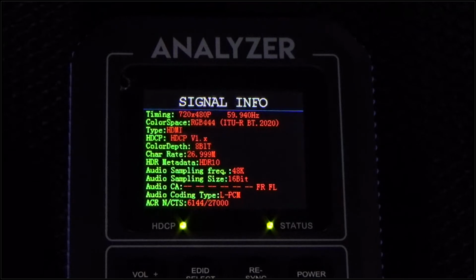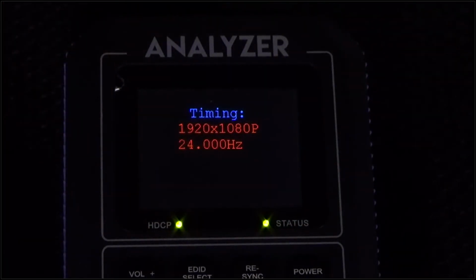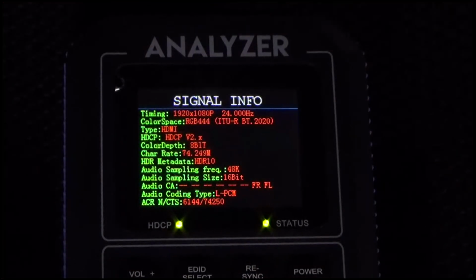In order for me to do 2.2, don't forget, we cannot do an 8K resolution. So now we're going to go HDCP 2.2. The analyzer is going to resync with the generator. And drum roll, please. We're back to 1920 by 1080. I set it like that on purpose. And we press the info button. And now we have HDCP 2.x coming through. So, of course, right now, just for demonstration purposes, there's nothing in between the generator and analyzer. But if there were, you can start to see how valuable this stuff can be.